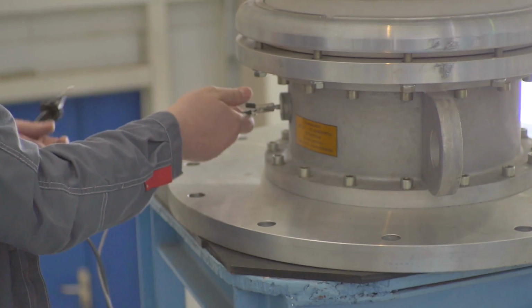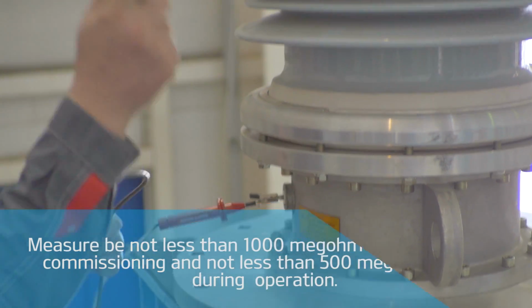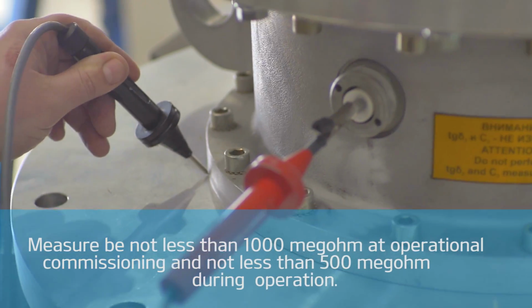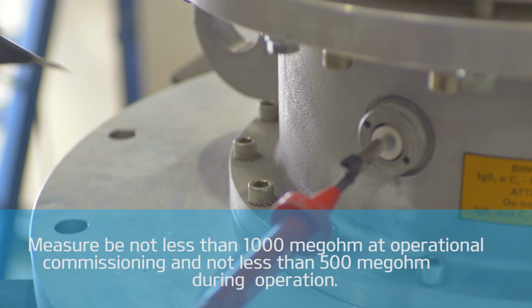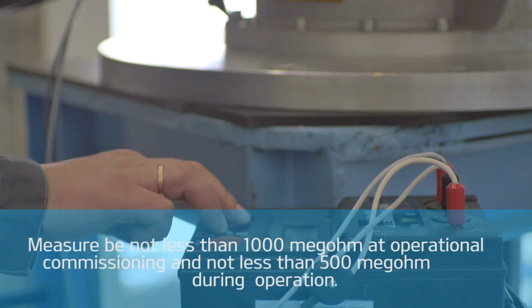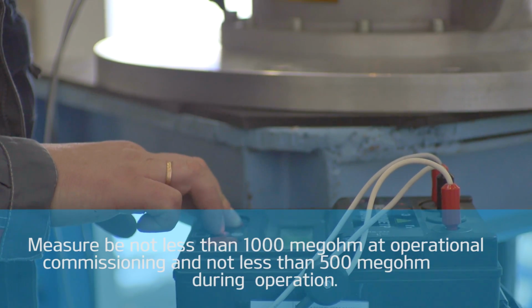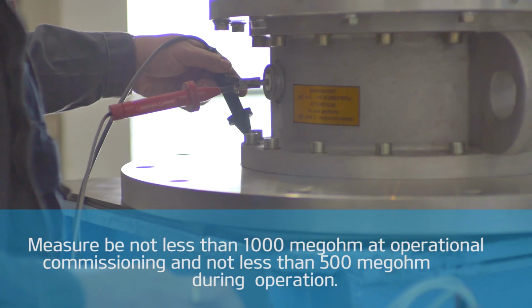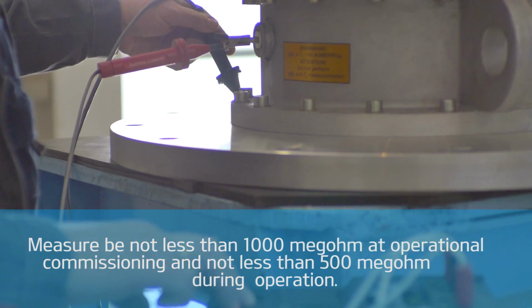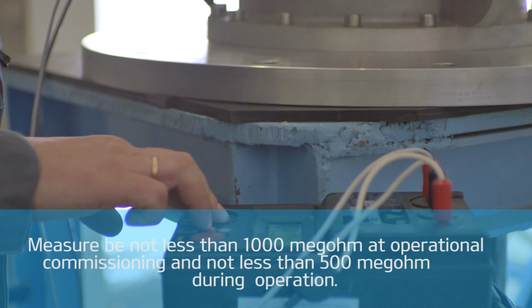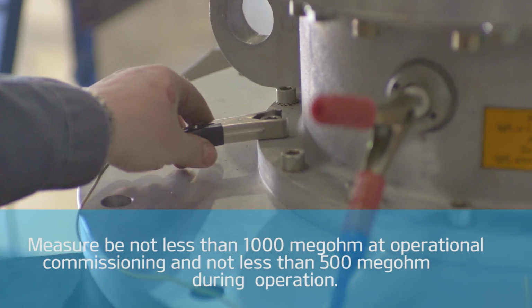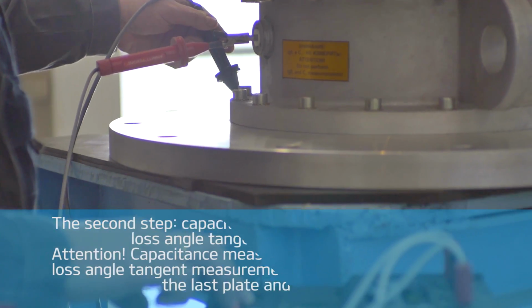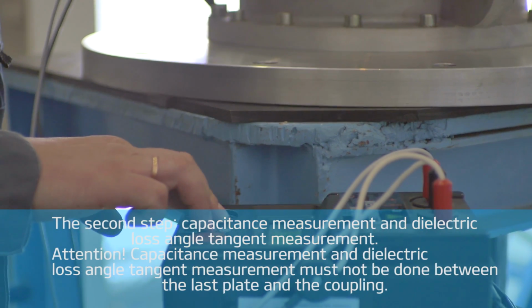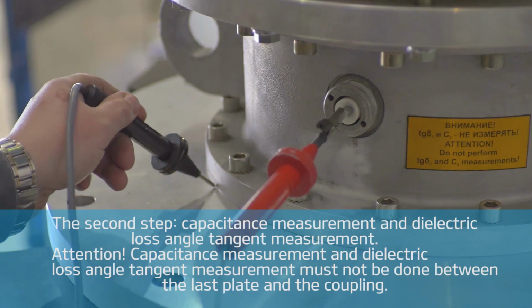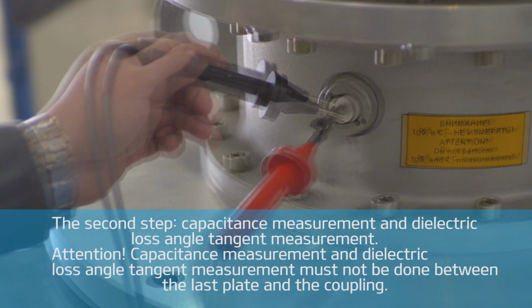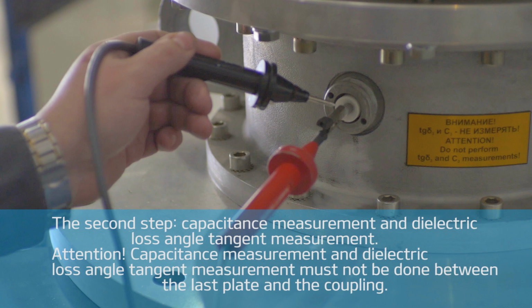The surface of the test tap insulation should be clean and dry. Use a 2500 volt megohmmeter to measure resistance on the test tap insulation. The resistance value must have a finite quality, circuit continuity, and be not less than 1000 megohms at operational commissioning and not less than 500 megohms during operation. The second step. Capacitance measurement and dielectric loss angle tangent measurement on the main insulation of the bushing.